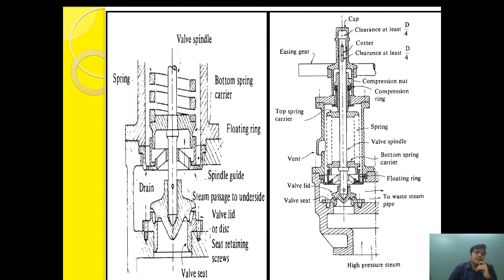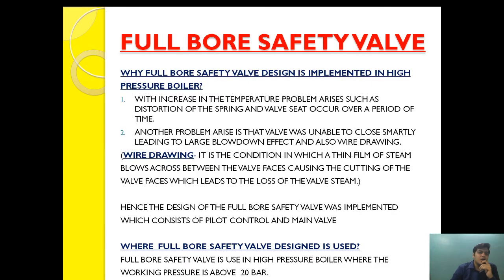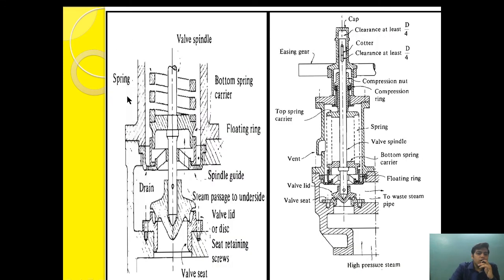When these springs are subjected to such high temperature, they are subjected to distortion, which affects the functioning of the valve and also reduces the overall service interval of the safety valve. Another problem is that the valve was unable to close smartly, leading to a large blowdown effect and also wire drawing. When the valve used to sit after steam pressure was released, a thin film of steam used to form which prevented the valve from seating very smoothly.